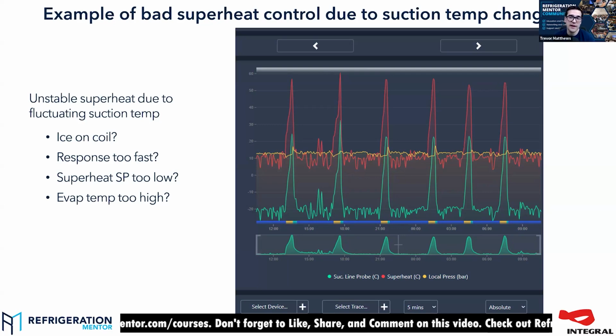So I've always said, as long as you check all the parameters, are they all correct? Are the coils clean? Are the fans running? All the basics done first, and then set the superheat 1 degree higher. You know what I mean? Warmer, and then one more. And every time, they send me the graphs, and you can see it start to stabilize because they're trying. It's just too much for that coil.